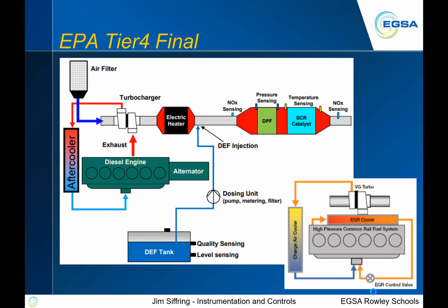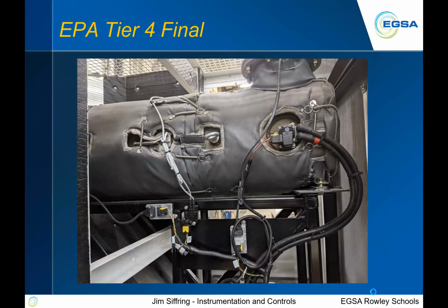Then we go into the temperature. We go into the catalyst, the SCR catalyst. So we look at the temperature going into the SCR, and if the catalyst is doing what it's supposed to be doing, that temperature should change. It should actually go up a little bit. And then we can look on the downstream side of that catalyst and see if the temperature has reacted in the direction we think it should. And finally, coming up the tailpipe, you see another NOx sensor, and that NOx sensor is going to say whether we're doing the job or not. So how much have we changed from the input side to the discharge side? So there's all those sensors we've been just talking about, and that's what it looks like in reality. This is a Cummins 15-liter engine, actually.